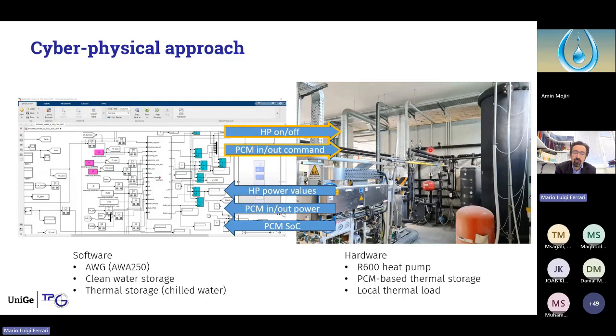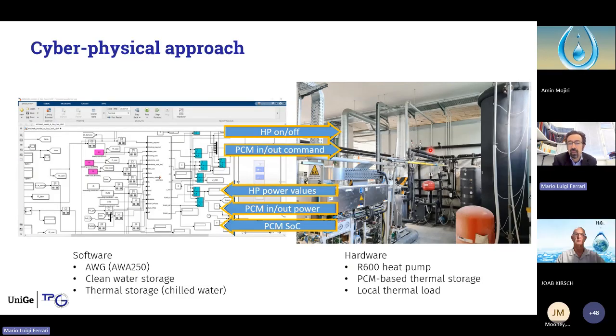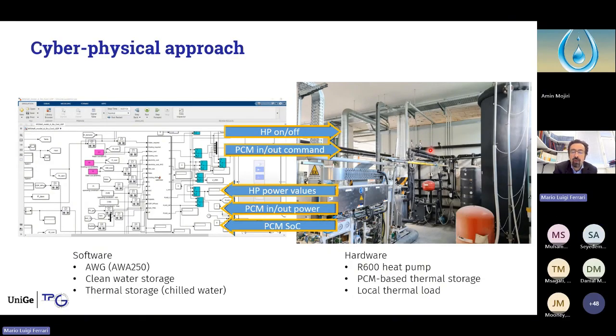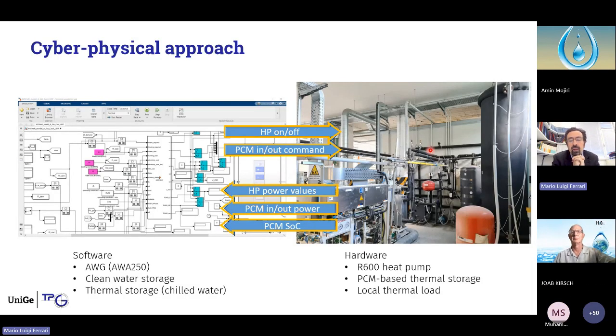On the other side, we have measurements like the heat pump power values measured second by second, the phase change material in-out power, because one side is the command, the other side is the actual measurement, and the phase change material state of charge. We have a state of charge measurement on the basis of pressure variation that is significant for giving us a signal for the state of charge of this system.